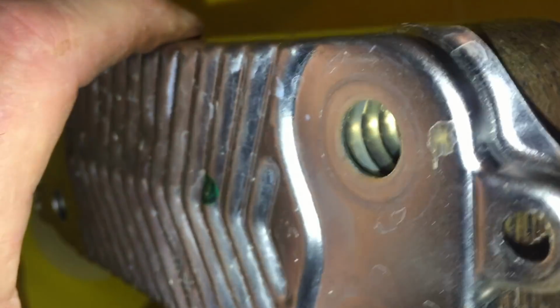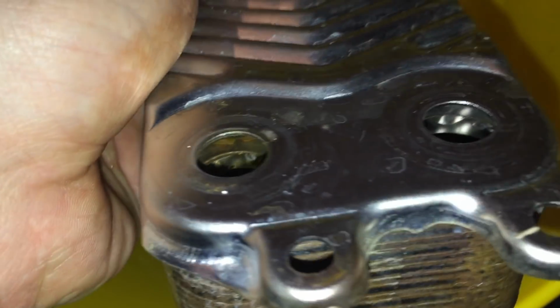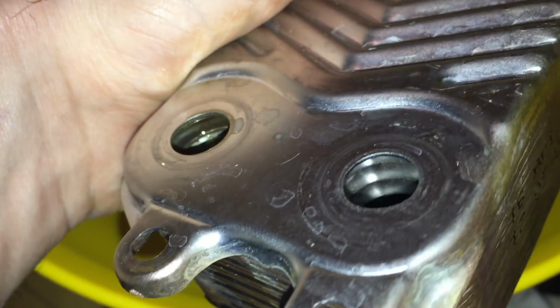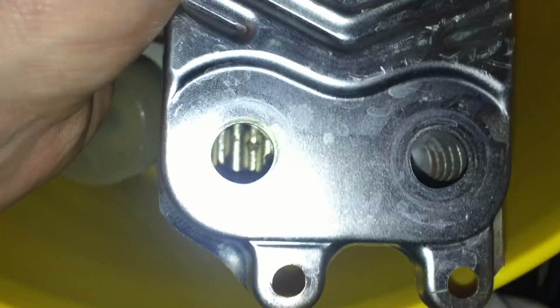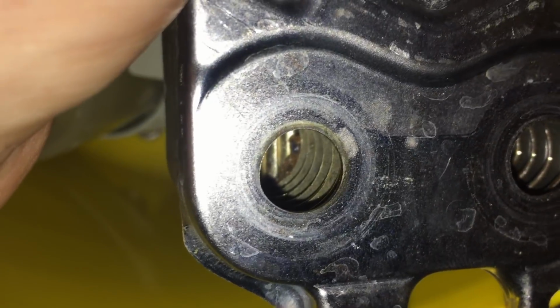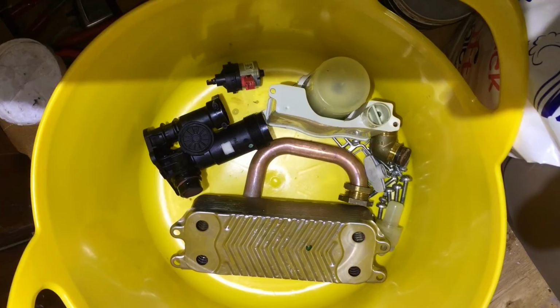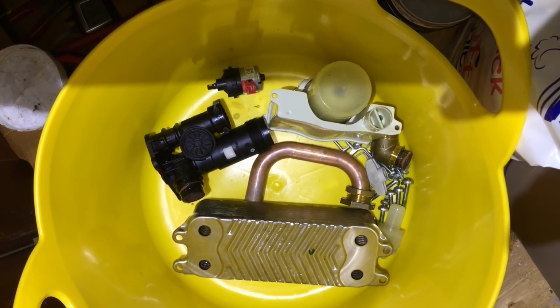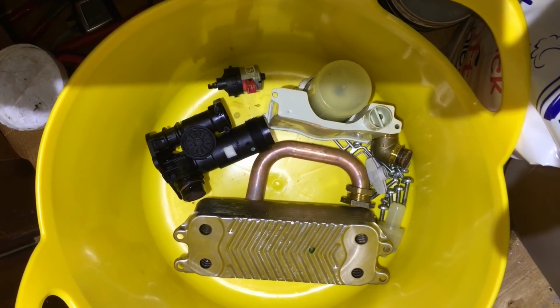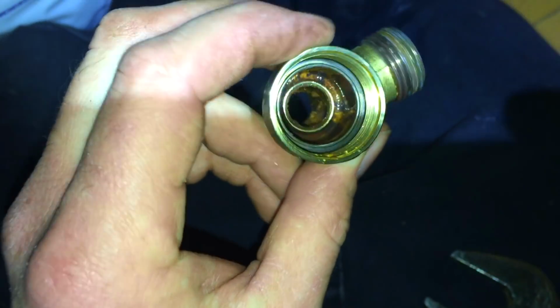Now this plate looks really clean. You'll see when I check the other holes here in a sec, there's a tiny little bit of debris you can see right in the bottom of it. Not this hole here, this next one. So this hole here on the left, can you see that tiny bit of debris at the bottom there? Now that is a good indication to me that that plate's going to have a lot of that in. This is all the stuff I removed to check. I couldn't find anything obvious, so I descaled the plate heat exchanger, basically, and that fixed it.